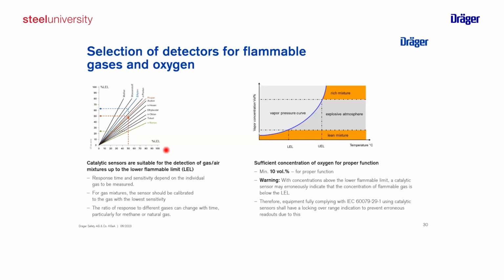Important is also to know that these catalytic bead sensors can only operate below the lower explosion limit, because here you still have a mixture of oxygen and the flammable gas, which can be combusted and give you a linear response. In the moment you cross the lower explosion limit, the signal you will get is not linear going up, it will go down, because the amount of oxygen is not sufficient anymore for this process to give you a linear reading. So sensors of this type are always limited to just the lower explosion limit. And we need a minimum of 10 volume % of oxygen so that we can still create this combustion process.